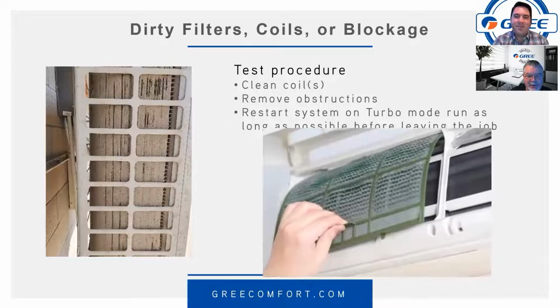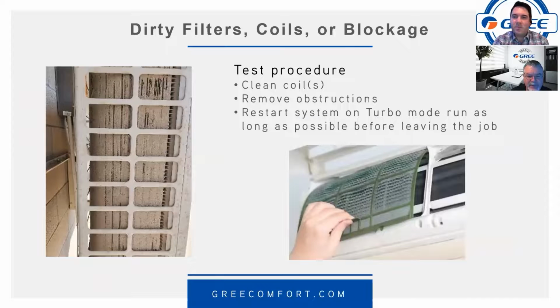And then we've got some dirty filters here. Those are pretty dirty. If the filters are that dirty, you think the coil might be dirty? Oh, most certainly. I bet it probably is. Yep. Once you clean these things, we would recommend you start the system in turbo mode, because if you power down, the E1 is going to clear. So restart in turbo mode and let it run as long as possible before you leave the job, because if that E1 pops back up, then you're back out there on another callback, and that's not good. Hopefully this is a service call that you can charge for.